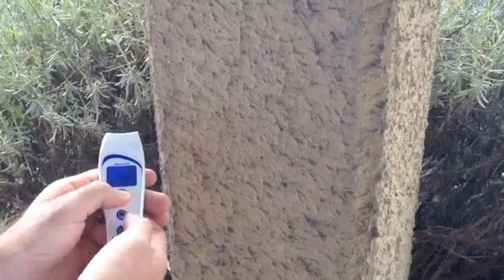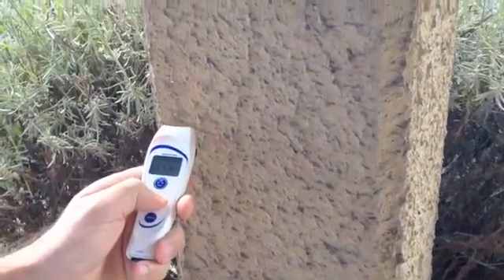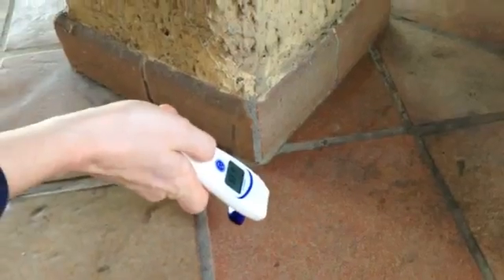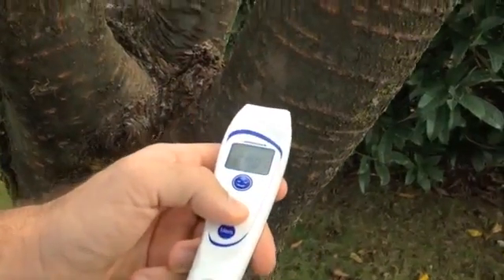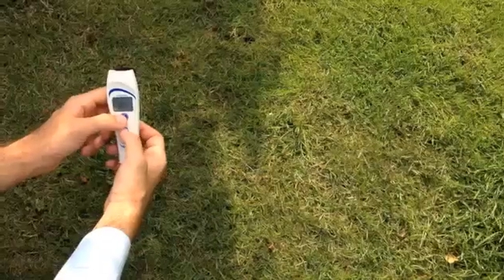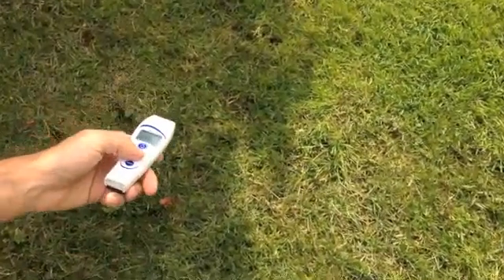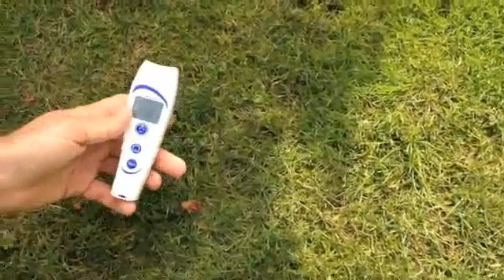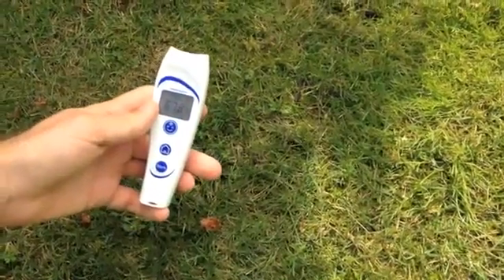If you need to take the temperature of people outdoors, you can make the manual quick calibration on an external building, on the floor, or on a trunk. Be sure that they have a temperature similar to the environment temperature, not directly exposed to sunlight or to heating or cooling sources. Then you can go directly to the forehead.